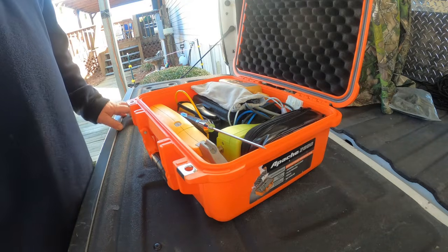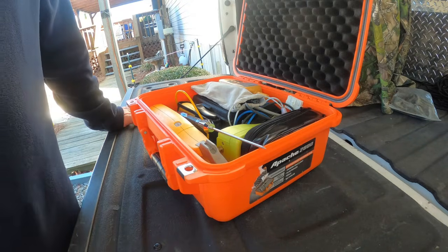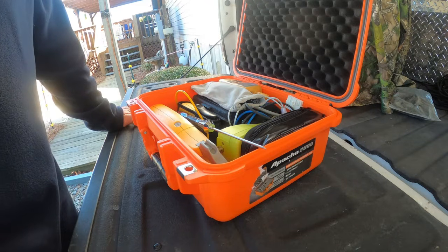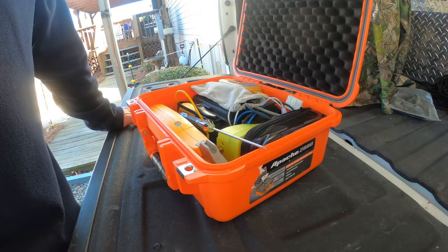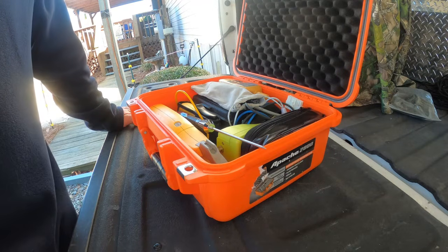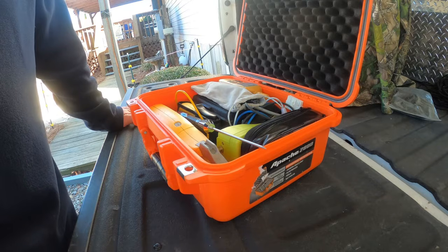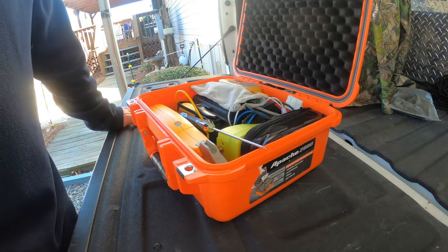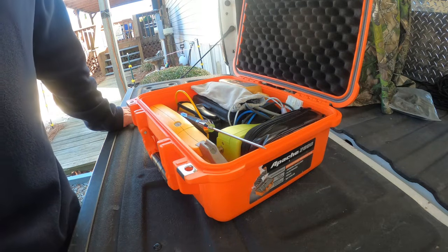So when you're troubleshooting those, you check your capacitor. Maybe your capacitor is okay. It's a 5, a 7.5, a 10. Capacitor is checking okay. Motor's still not running. You can ohm out your windings. See if you have an open winding. See if your motor's hot. Typically, if it's locked or seized, you're going to have a hot motor. You're going to have a high amp draw. It's going to be trying to pull amps, but it's not running.